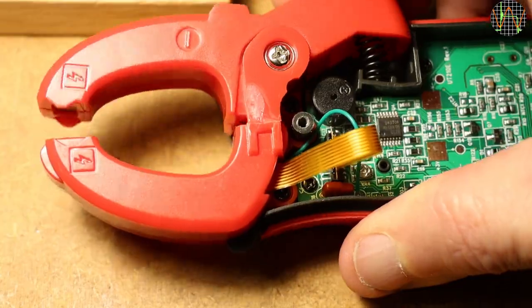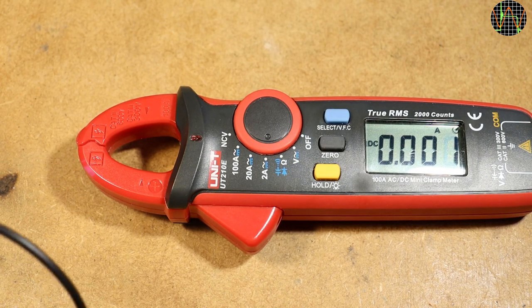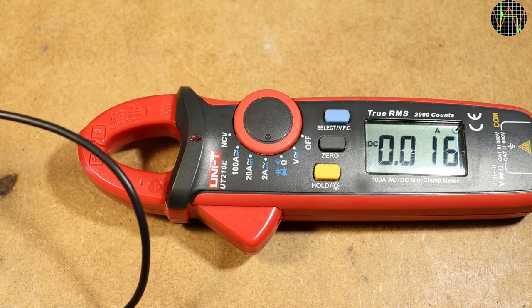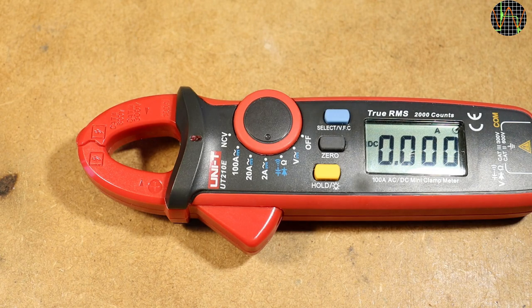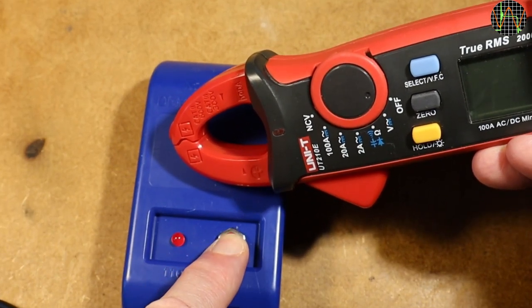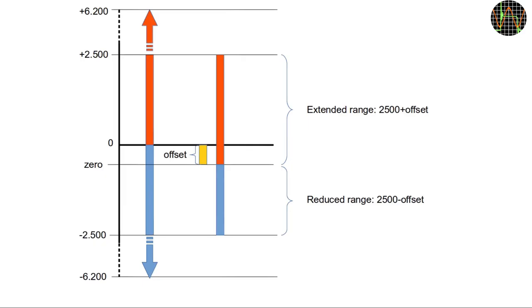If you have to do a similar repair, use something to keep the jaws open like this to avoid getting glue into the gap between the jaws. Avoid if possible proximity to neighboring conductors. This wire carries a DC current of just 2.5A and you can see that it influences the reading even though it is outside the clamp. Occasionally demagnetize the clamp because the iron core will slowly pick up residual magnetism from the induced fields.